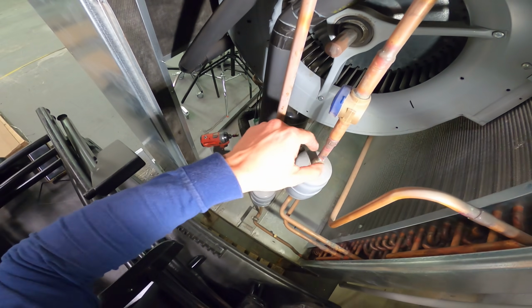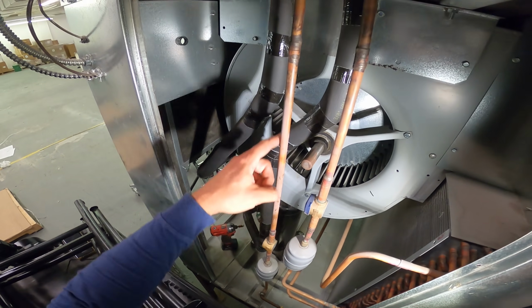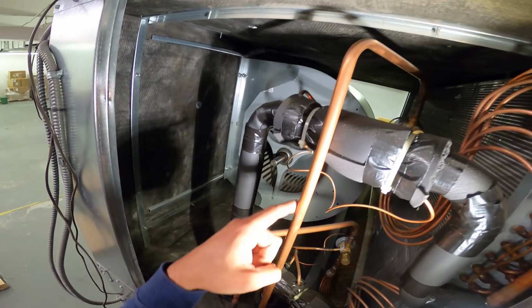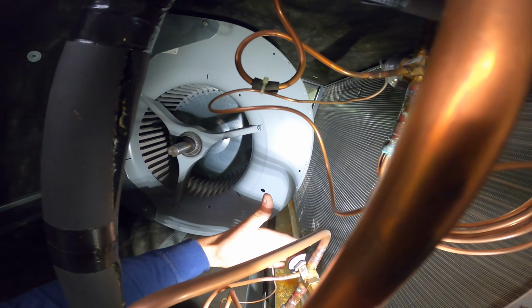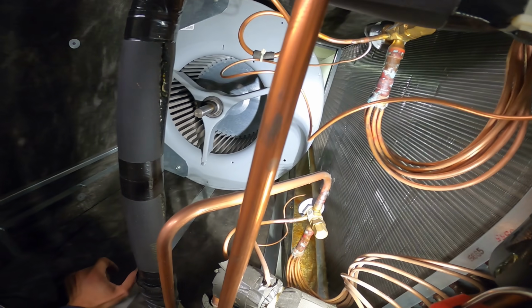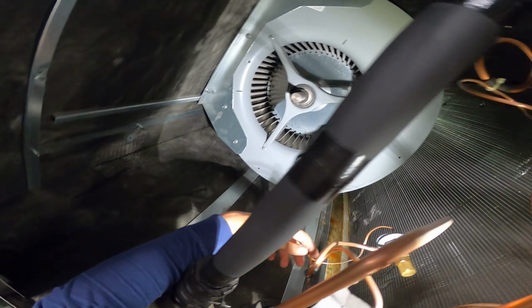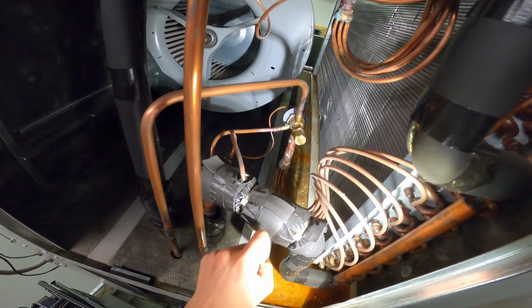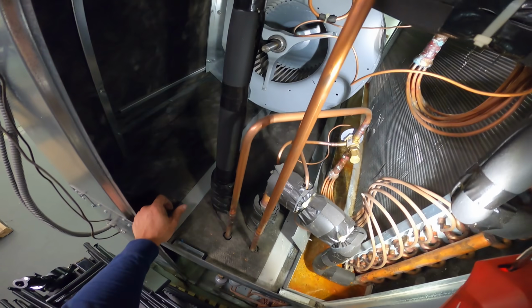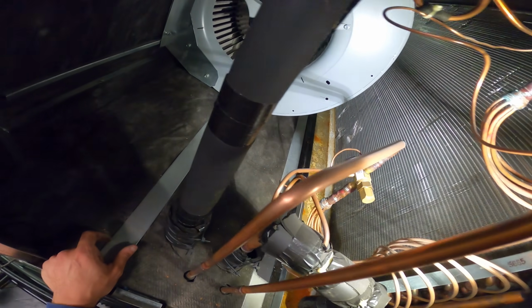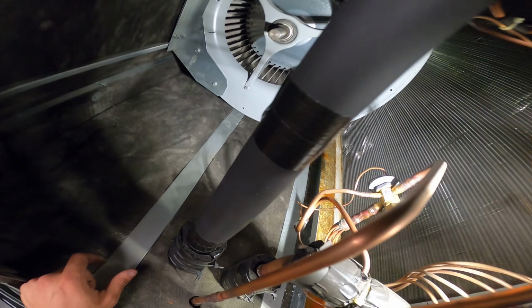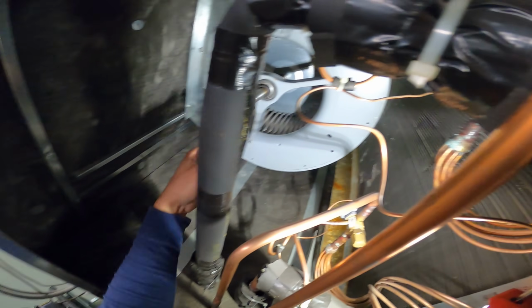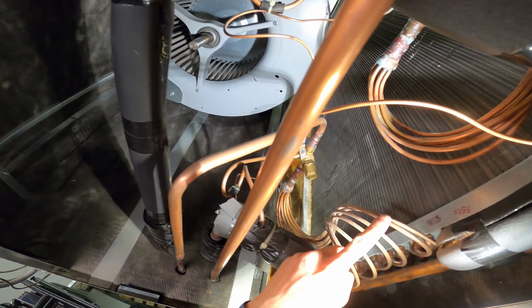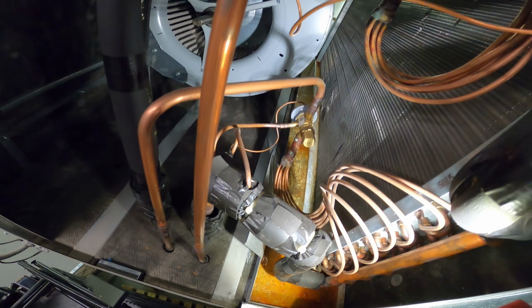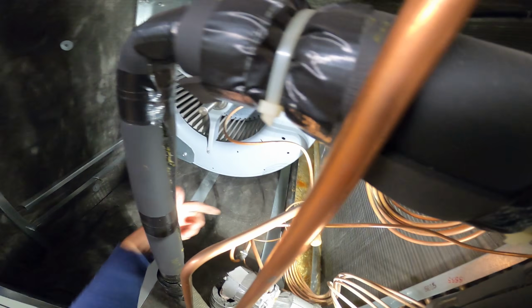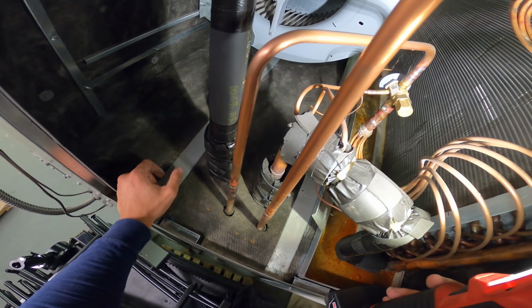All right, so these are our filter dryers, and we know that's always going to be on our liquid line. Following the circuit, it comes up, one here and one here, and you can see these components right here. We have two expansion valves. You can see that off the head there's a little bulb that comes out and gets strapped to your suction line, and that is called a feeler bulb, and this is a thermostatic expansion valve. Thermostatic or thermal expansion valve, people really have different names for it. Usually it's two pipes. You've got your liquid line coming in, then it comes out through here, and this is actually a distributor, and it distributes the refrigerant into your evaporator coil. But if we follow, we actually have a third line here, and that is an equalizer, and it helps balance the system, and that also gets tied into your suction line.